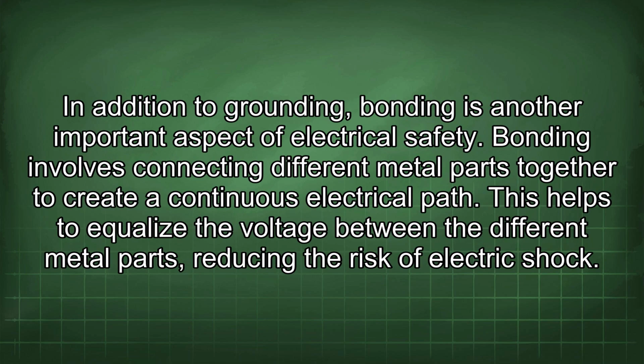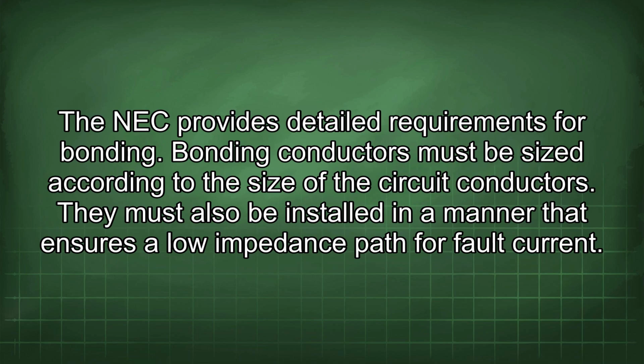In addition to grounding, bonding is another important aspect of electrical safety. Bonding involves connecting different metal parts together to create a continuous electrical path. This helps to equalize the voltage between the different metal parts, reducing the risk of electric shock. The NEC provides detailed requirements for bonding. Bonding conductors must be sized according to the size of the circuit conductors. They must also be installed in a manner that ensures a low impedance path for fault current.